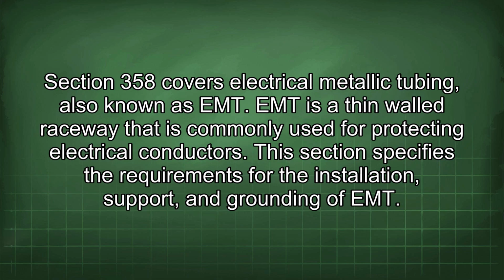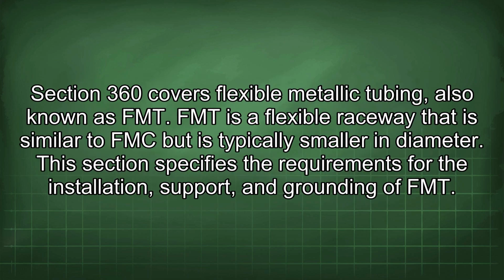Section 358 covers electrical metallic tubing, also known as EMT. EMT is a thin-walled raceway that is commonly used for protecting electrical conductors. This section specifies the requirements for the installation, support, and grounding of EMT. Section 360 covers flexible metallic tubing, also known as FMT. FMT is a flexible raceway that is similar to FMC but is typically smaller in diameter. This section specifies the requirements for the installation, support, and grounding of FMT.